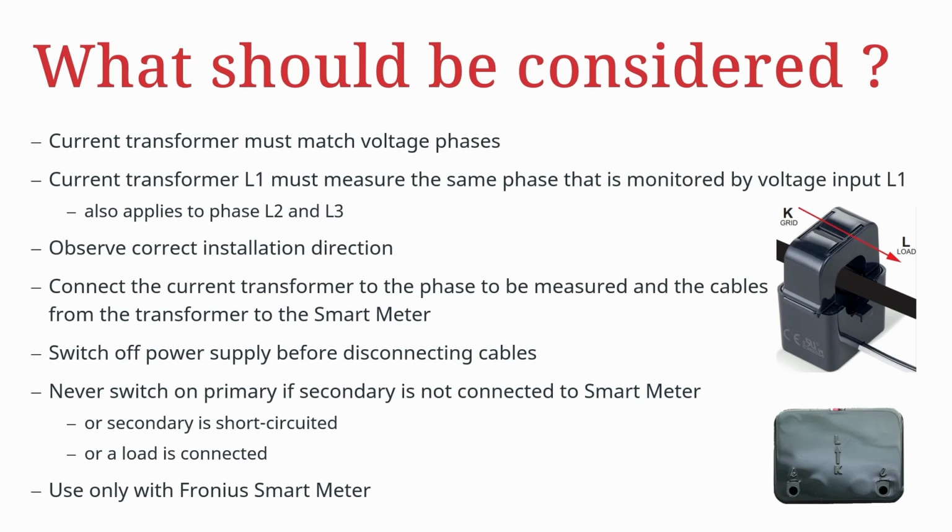Yeah, and what are now the most important points and what should be considered when you are using the CTs? The current transformer must match the voltage phases. This means the current transformer L1, for example, must measure the same phase that is monitored by the voltage input of phase 1, so of L1. This also applies to the other two phases, L2 and L3.